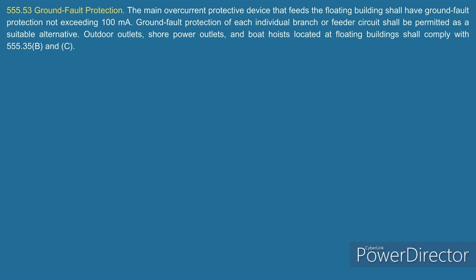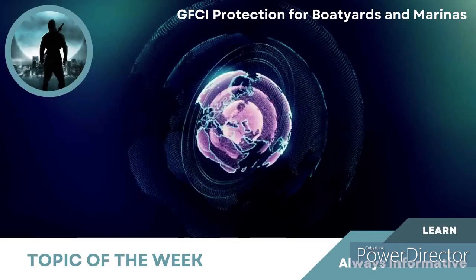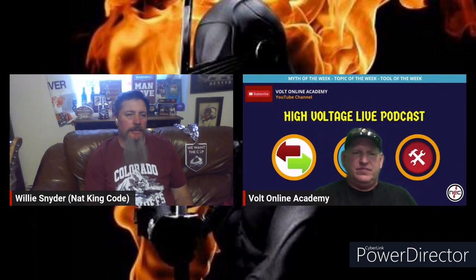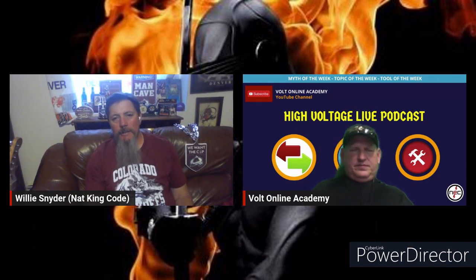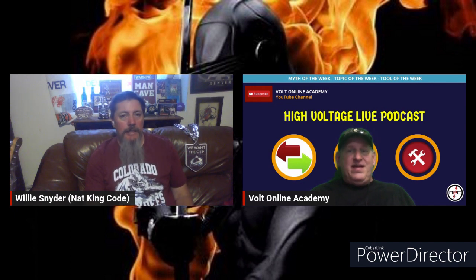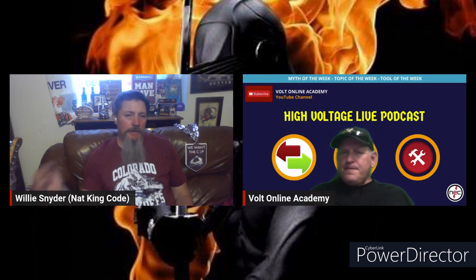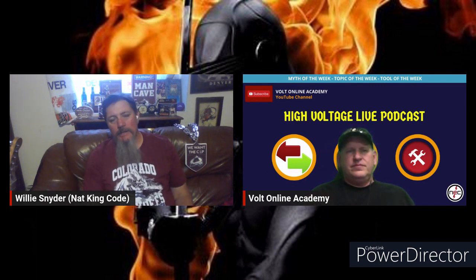Receptacles. Yep. And what we run into here is a really good way to illustrate it, James. I really like it. Let's say you have a building where they're selling sandwiches or something. Now you have a hardwired AC unit out there, and you don't have Class A protection on it. But guess what you have? If for some reason something happens, you have a 100 milliamp GFPE on that. That 100 milliamp GFPE is going to save somebody's life on that AC unit. Sure it is, because if you have a problem, like in the case of Bontrell Pergo, he jumps the fence, he lands on the AC unit, the 100 milliamps trip, and Bontrell Pergo walks home.